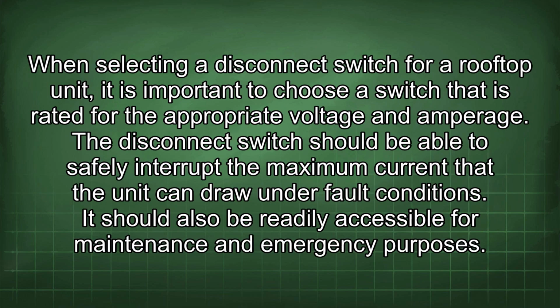When selecting a disconnect switch for a rooftop unit, it is important to choose a switch that is rated for the appropriate voltage and amperage. The disconnect switch should be able to safely interrupt the maximum current that the unit can draw under fault conditions. It should also be readily accessible for maintenance and emergency purposes.